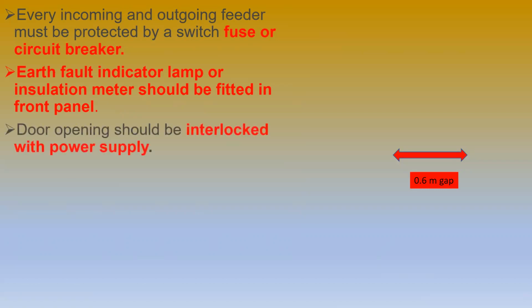Next, the door opening should be interlocked with the power supply. So whenever we open the door, there should not be power supply. But if by mistake you open the door without tripping the supply, an automatic trip will be there. That is interlocked with the power supply. Automatically, it will trip off.